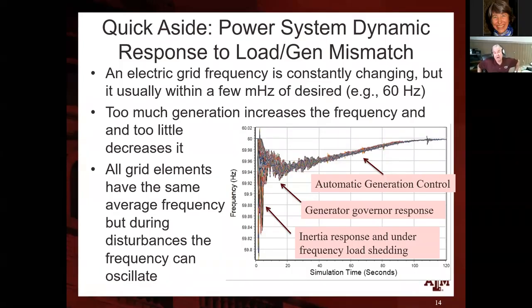If we lost a large amount of generation, what would happen is the frequency would start to drop. As the frequency starts to drop, what's going on is we are getting energy from the inertia stored in the rotating masses of the generators. Usually there's enough energy there that within seconds, the frequency starts to stabilize. If it doesn't, if the loss of generation is too much, then we have relays out there that will drop load if the frequency goes too low. And each interconnect has relays set for particular frequency cutoffs where they will drop load if it goes too low. And that helps to arrest the frequency decline and hopefully stabilize the grid.